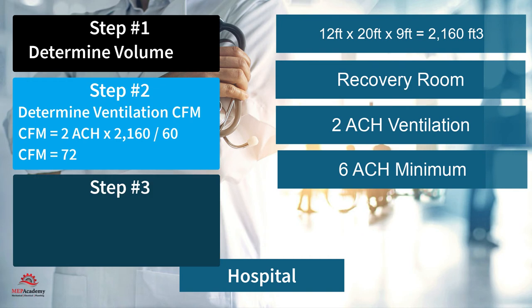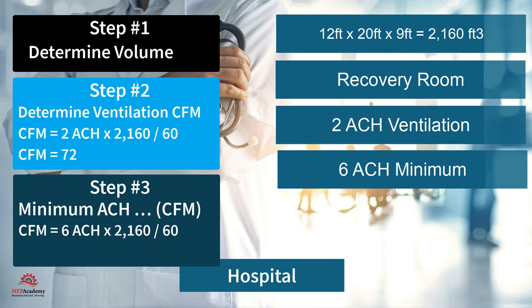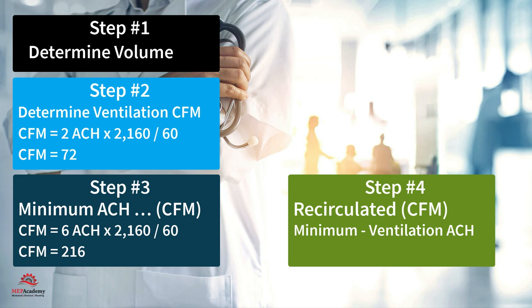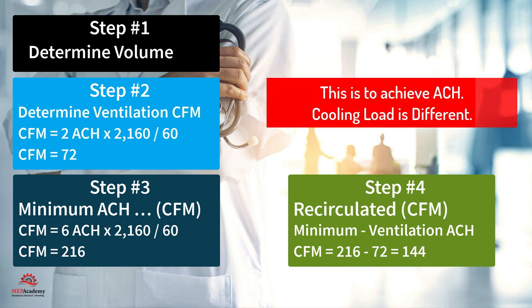Step 3 is to determine the required minimum CFM. CFM equals six air changes times 2,160 cubic feet divided by 60, giving CFM equals 216. Step 4 is to determine the required CFM to be recirculated through the HVAC equipment. Minimum air changes per hour minus ventilation air changes per hour equals recirculated air changes per hour. Recirculated CFM equals minimum CFM of 216 minus ventilation CFM of 72, giving recirculated CFM of 144. You can see that the same size room at two different air change rates makes a huge difference in the volume of air that must be circulated.